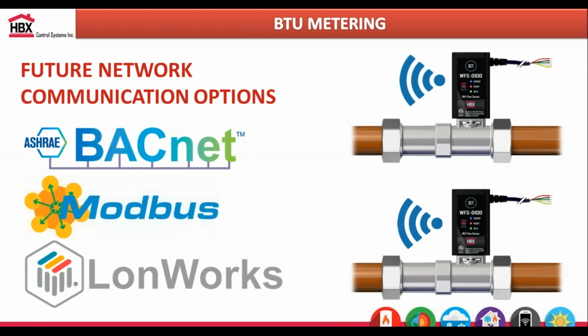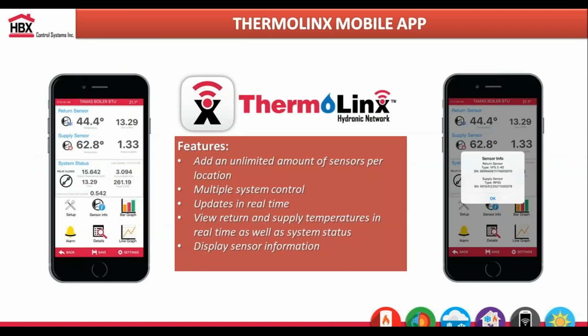Other network options: through the SensorLinx, we can connect to BACnet or Modbus using our open API on our servers to connect to these building management systems. This is something we're going to be adding to our 550 series later on. So if you need our snowmelt controller or our boiler controller connected to BACnet, it's going to be through this open API done through our network. That's what we've already built for the SensorLinx heat meters.